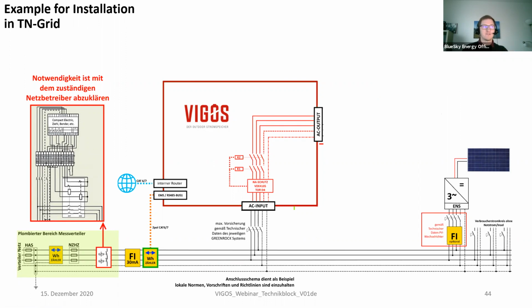The main focus of the system is to give the loads as much sustainable energy as possible. So first, provide them with the PV and only charge the battery if you have excess energy going to the grid. And if the PV is gone, supply the loads via the battery.